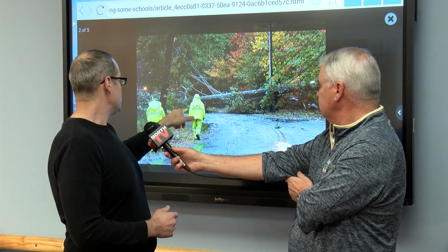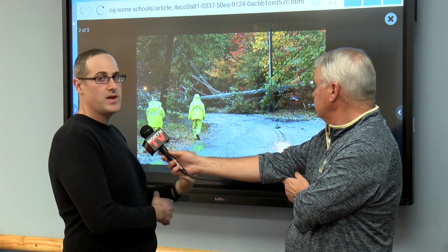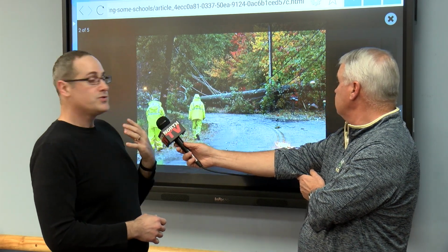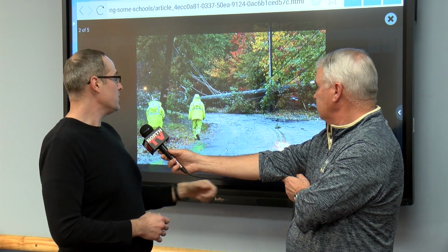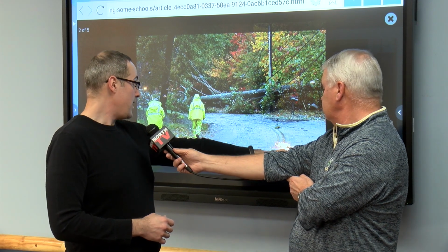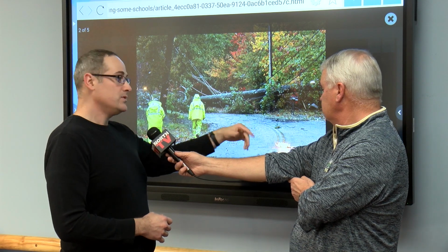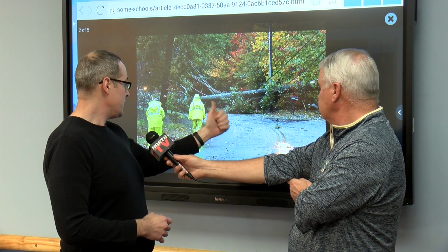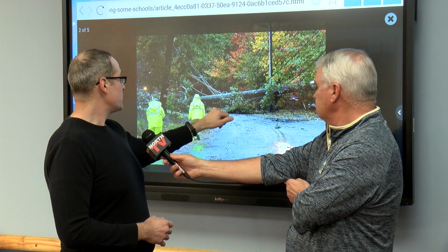On the other side of this, there are transformers. We have a bunch of wire, primary, secondary, cable, everything tangled up in here. What it does to poles closer to us in this photo is it actually yanks the primary line. It's 13,000 volts, and when it yanks it, it's so dramatic that it actually snapped live. So we had a burning cable here, which moments later was de-energized at our substation and switched out. Next, the tree gets removed. Tree crews chop it up, get it out of there, and then our crews can get to work.